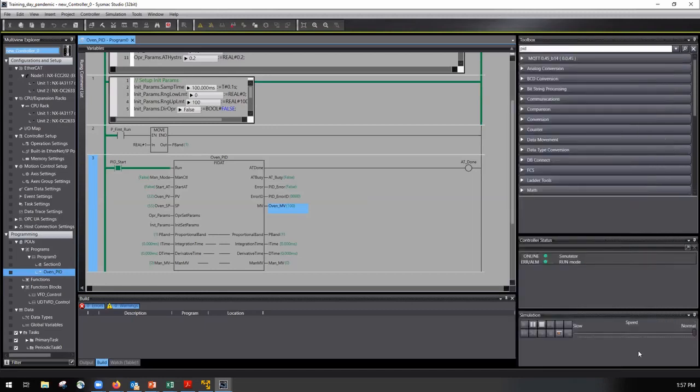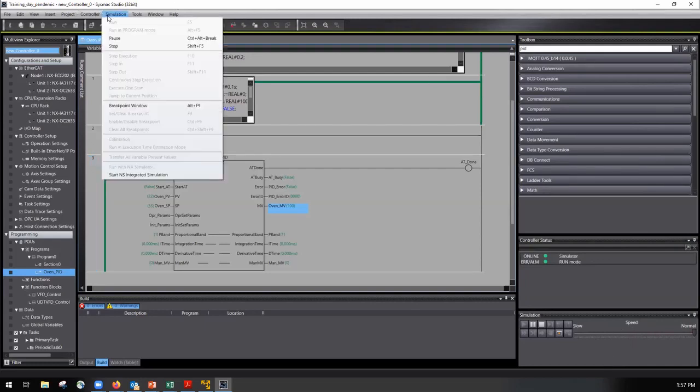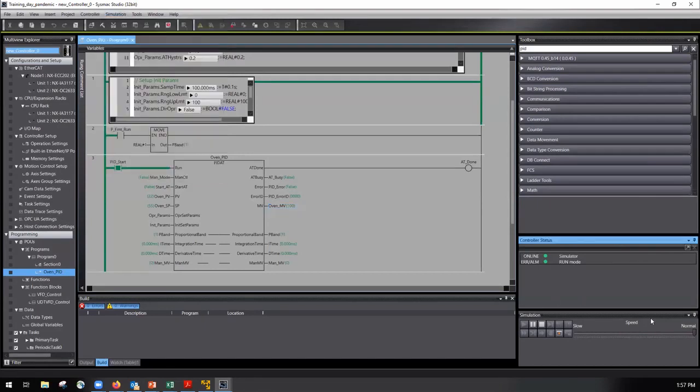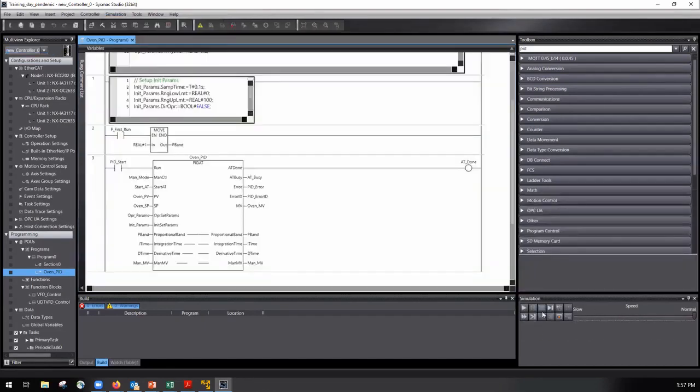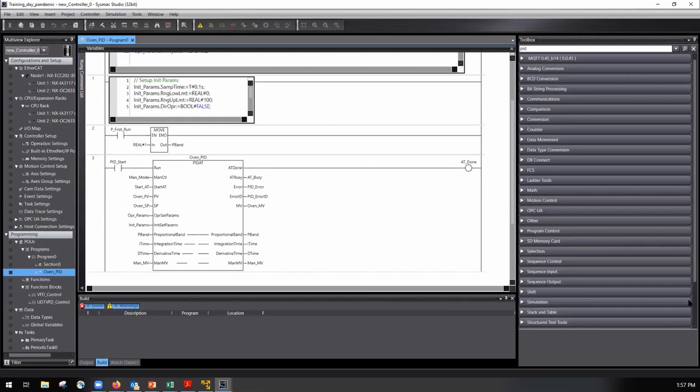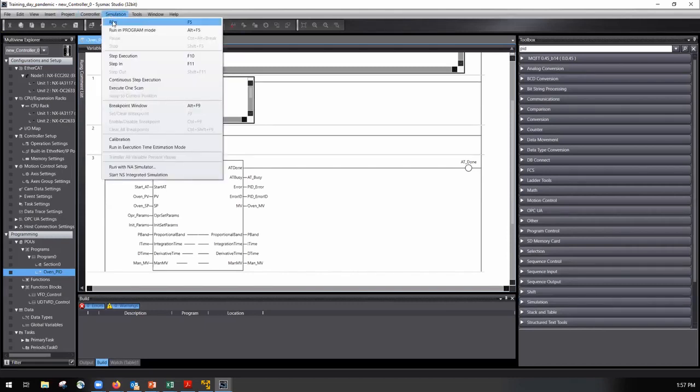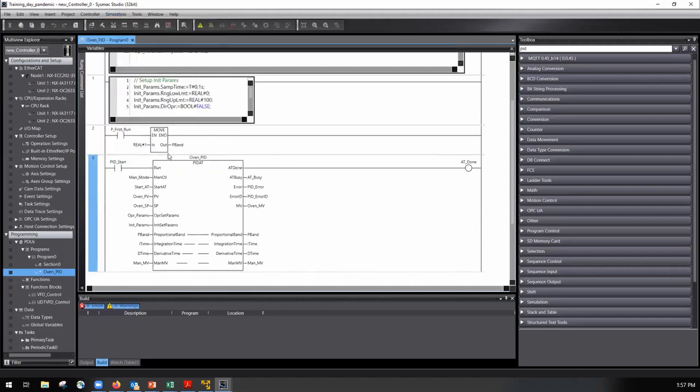Your simulation, did you by chance run your simulator in program mode? Let me check that. We just stop the simulator, close the simulation window altogether, and then just restart it and make sure that it's run instead of run in program mode, because it almost sounds like logic isn't executing in yours, especially if that 1 wasn't sent to the P-band.